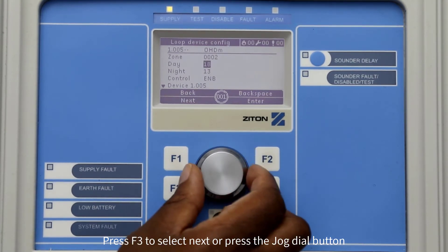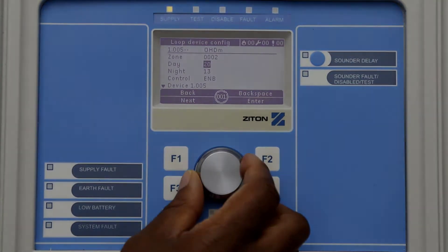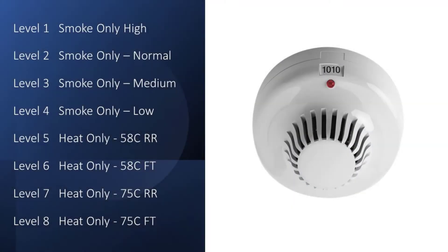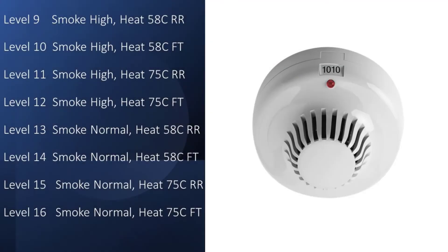For a multi-sensor there are 27 possible profile settings. Profile number one is a smoke-only profile and is the most sensitive smoke option. Profile number four is a smoke-only profile and is the least sensitive smoke option. Profiles numbers 5 to 8 are heat-only options. Profiles 9 to 27 will activate in a fire condition with either smoke or heat.